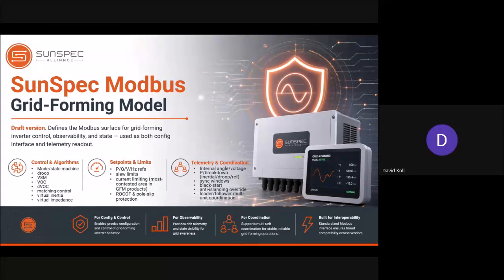That's why I tried to emphasize in there that we need this to support the existing 700 series. If we wanted to just blow this out and say we're just looking at a plant controller, those exist across the board. If we say non-utility supporting, it's just going to go offline in an island state, that's easy. We have all of that. To try to get the grid forming model in place to support the grid following model without it taking over, that's the trick.